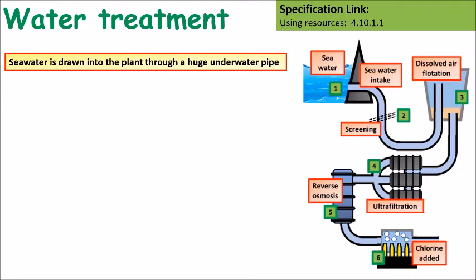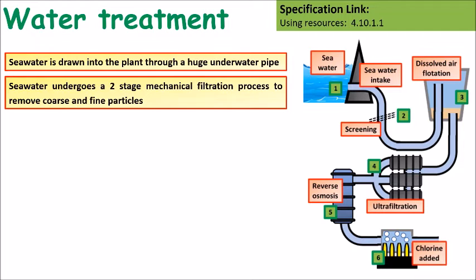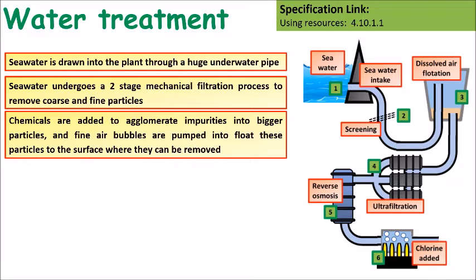The process of desalination starts off with seawater drawn into the plant from the sea. The seawater undergoes a two-stage mechanical filtration process that removes coarse and fine particles such as sand and grit. Chemicals are added to stick impurities together and fine air bubbles are pumped in to float these particles to the surface where they can be scraped off and removed.